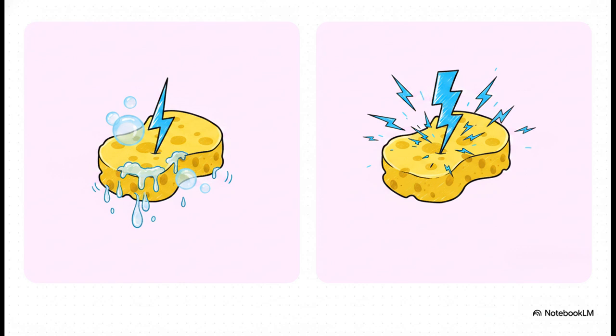Well, when generators just sit idle, especially if you're in a humid or coastal environment, the stator winding insulation acts exactly like that sponge. It absorbs moisture right out of the air, and this moisture creates an unwanted conductive path. So a Megger test basically pushes voltage through the insulation to catch exactly this kind of slow, reversible problem before it blows up into a massive winding failure.